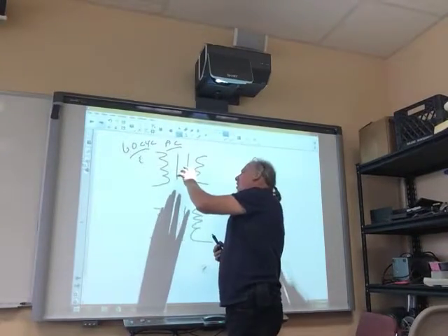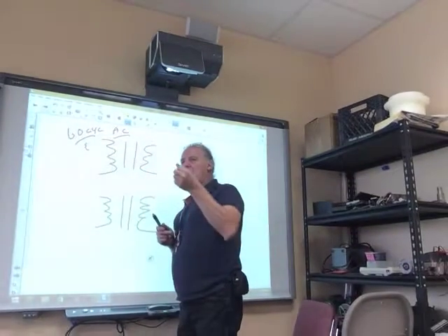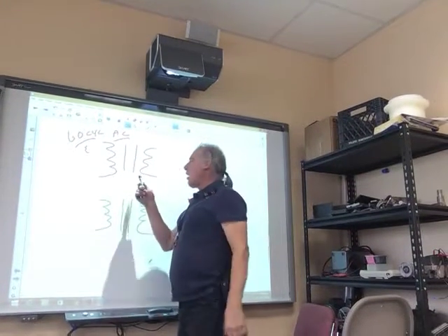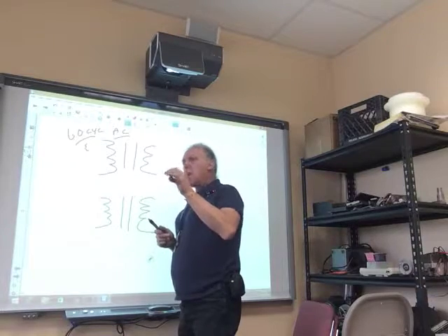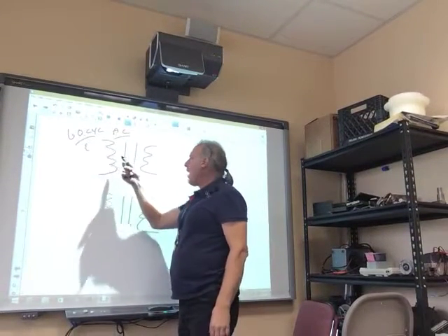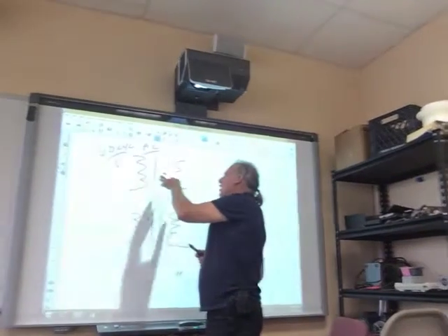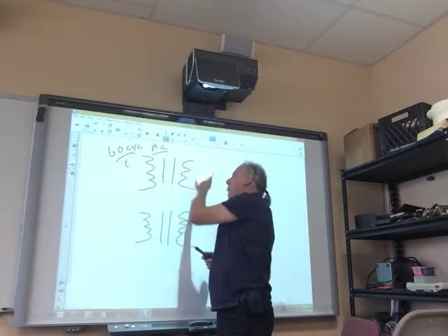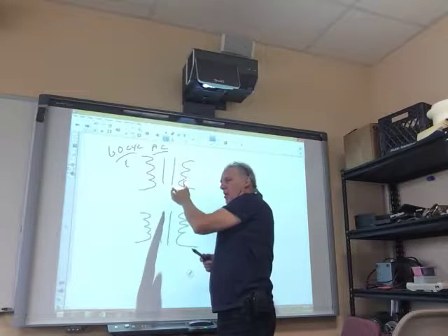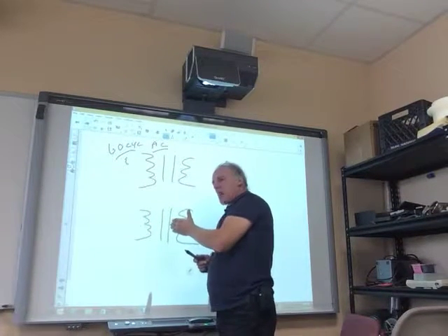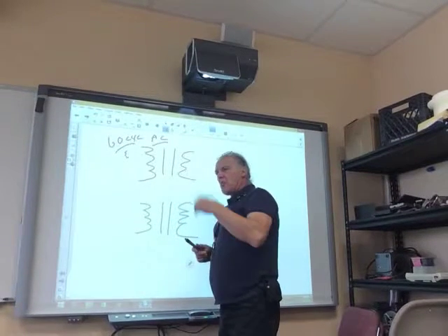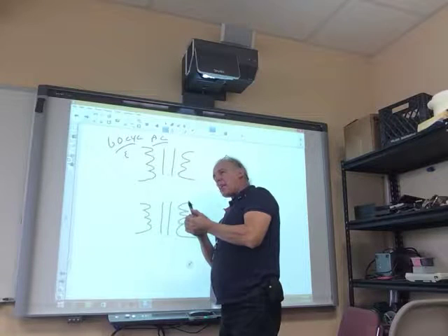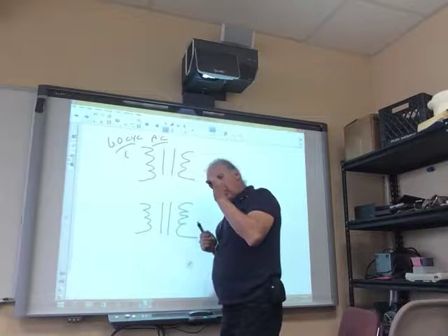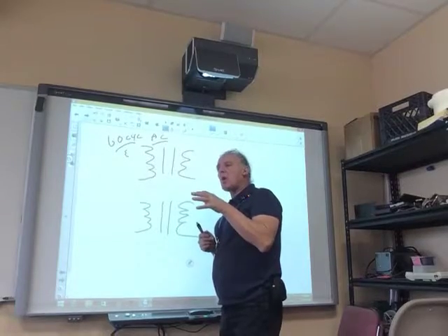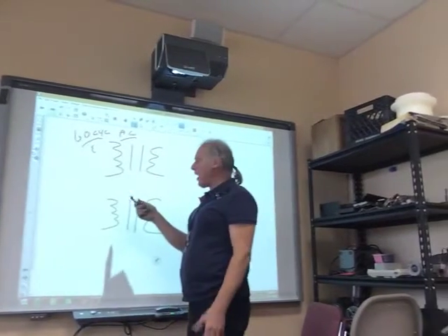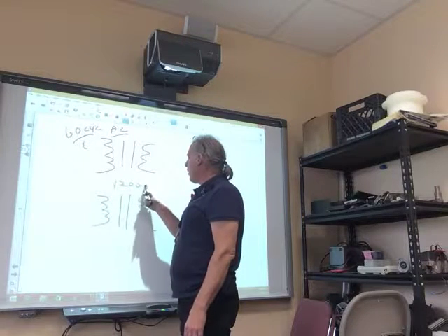So across this junction, we use lamination because solid iron doesn't flip back and forth very fast. Laminations are thinner, less iron - they can change more quickly at 60 hertz, and the inductance can inductively channel the power from the primary to the secondary through the core. Now, higher frequency transformers can't use laminations, so they go to iron filings glued together. Iron filings are little tiny pieces of iron, so they change very quickly. So now we can build a transformer that's, say, 1200 cycles.